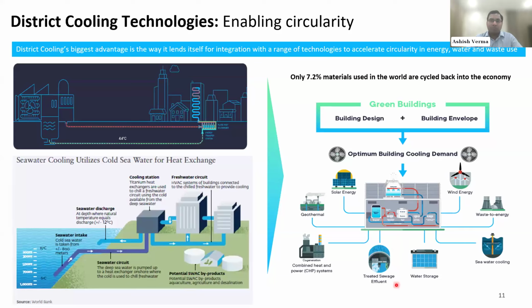District cooling systems can also be integrated with combined heat and power systems, a cogeneration or trigeneration plant, which is in fact one of the recommendations of the ICAP. And one important thing we have done recently for Tabreed is we have commissioned a geothermal plant where we are providing cooling through a geothermal system. We are generating hot water through geothermal means at 90 degrees and operating a vapor absorption machine, which is very different from the vapor compression system conventionally used. And that's how we can integrate all these systems. But this is not at all possible when you talk about standalone buildings or standalone cooling plants in the middle of downtown, the middle of the city.